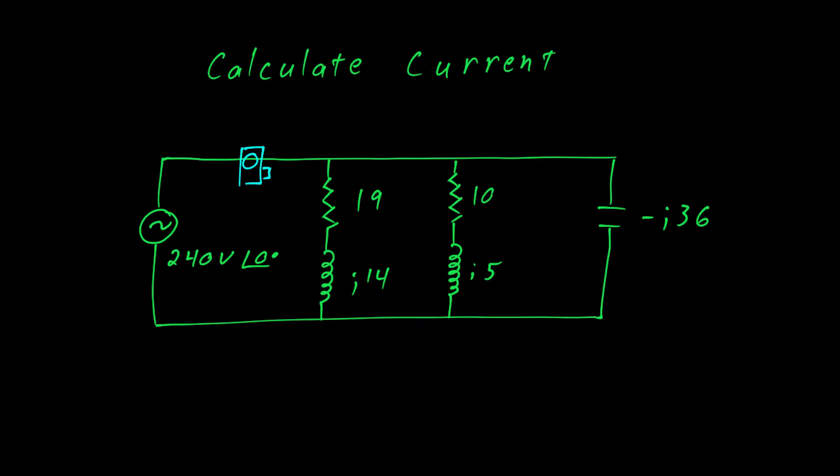In this problem we're asked to calculate the total current as measured by the amp clamp on this line. The circuit consists of several parts. We have a 240 volt source, this is a motor, this is another motor with a higher horsepower, and over here is a power factor correction capacitor.